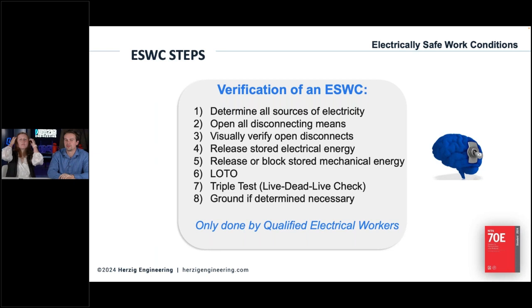So what are those steps? So they are determine all sources of electricity, open all disconnecting means, visually verify the disconnects have been opened or released, release stored electrical energy, release or block stored mechanical energy. Oh, there's LOTO. Wow. Yeah. We just talked about that. See, they go hand in hand. Yep. And then you've got the triple test, live dead, live check, which you need to do Lotto first in order to really do that. And then ground if determined necessary.